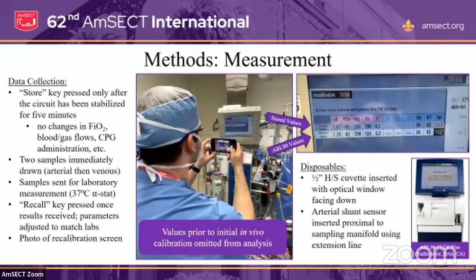And as I said, we used a half-inch venous cuvette with the optical window facing down to minimize interference from air coming down the venous line. And the arterial shunt sensor was inserted proximal to the sampling manifold using an extension line. And as I said before, the values prior to that first in vivo calibration were omitted from analysis.